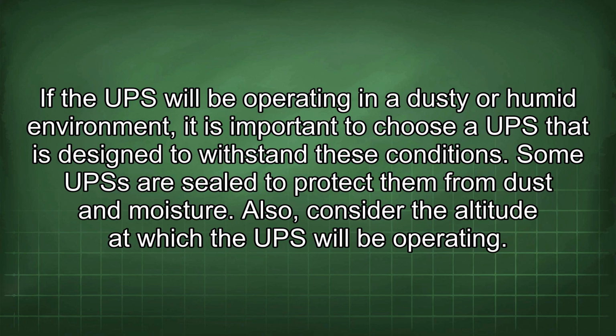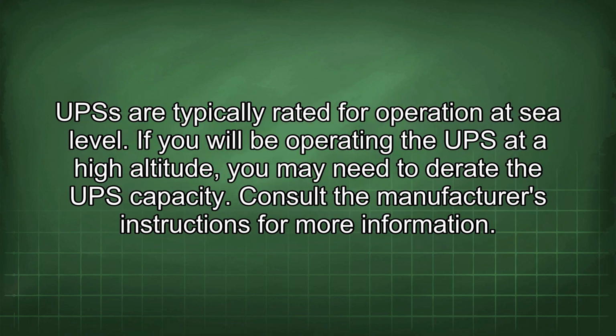If the UPS will be operating in a dusty or humid environment, it is important to choose a UPS that is designed to withstand these conditions. Some UPS are sealed to protect them from dust and moisture. Also, consider the altitude at which the UPS will be operating. UPS are typically rated for operation at sea level. If you will be operating the UPS at a high altitude, you may need to derate the UPS capacity. Consult the manufacturer's instructions for more information.